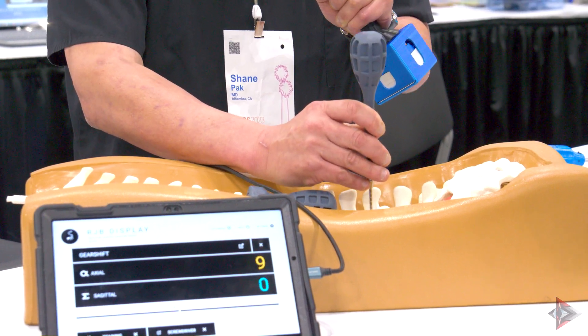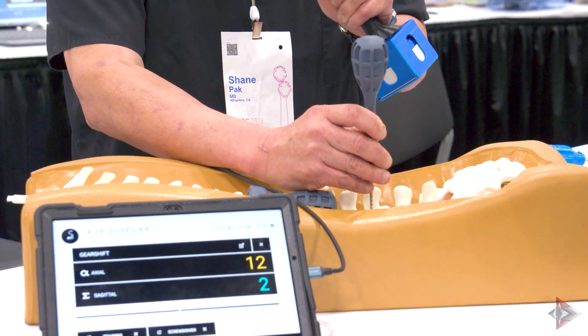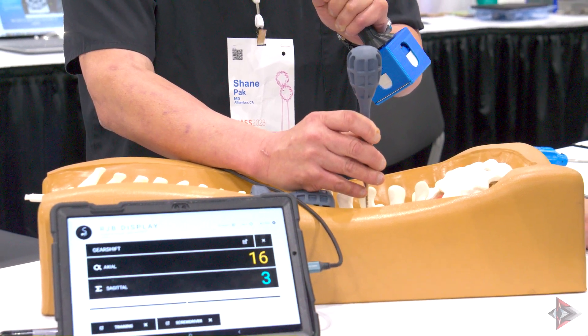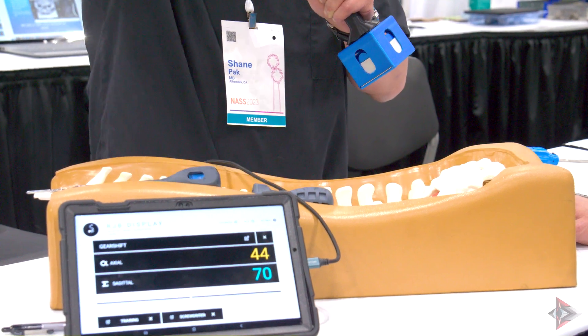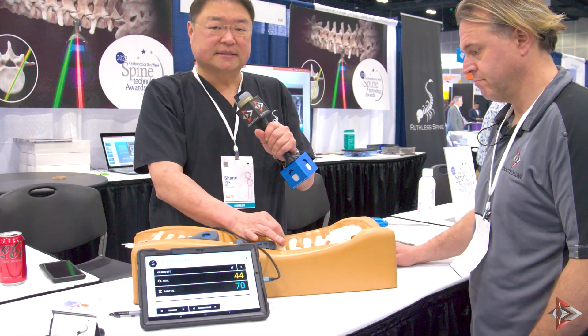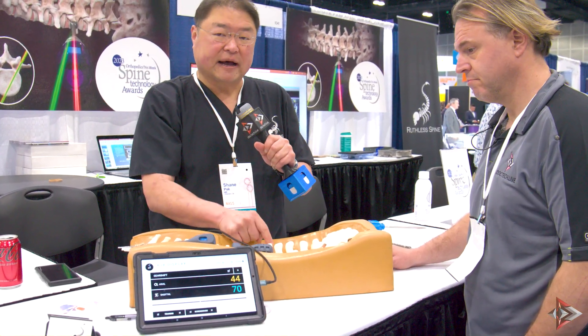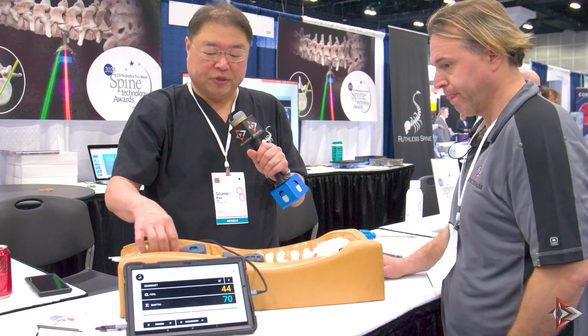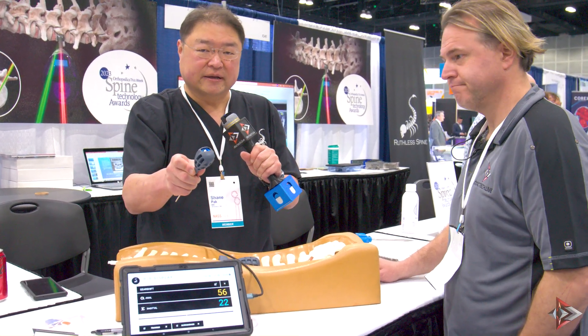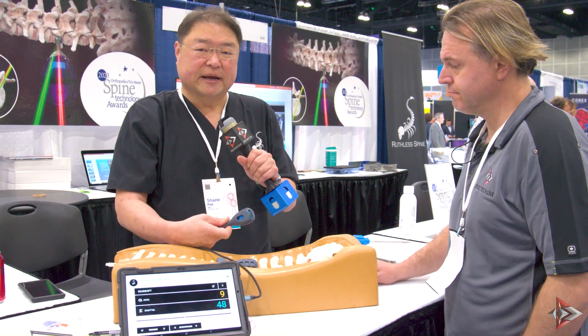How does the RJB register to the spine? The RJB module registers to gravity. I place the patient on the OR table, take an AP fluoro, and rotate the spinous processes until it bisects the pedicles. Therefore, the spine is registered to gravity, the module is registered to gravity, and by the transitive property of navigation, the module is registered to the spine.